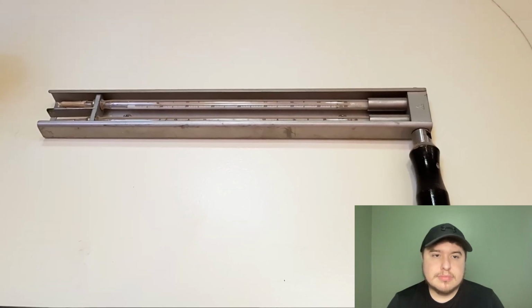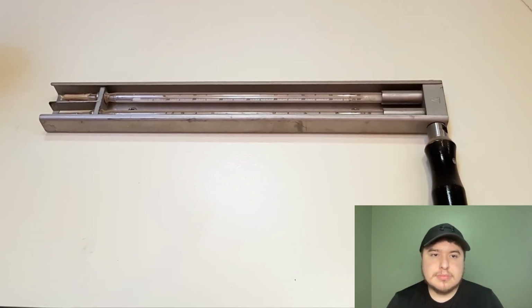You might think the outside air has just one temperature, but to cooling professionals it has two. One we call the dry bulb temperature is what you normally encounter. That's what shows up in the weather report. It's what's on the thermometer. But air also has a wet bulb temperature. If you soak the end of a thermometer and pass it through the air, that water will evaporate. The drier the air, the more easily water evaporates. This is why it feels so much hotter when it's also humid outside.